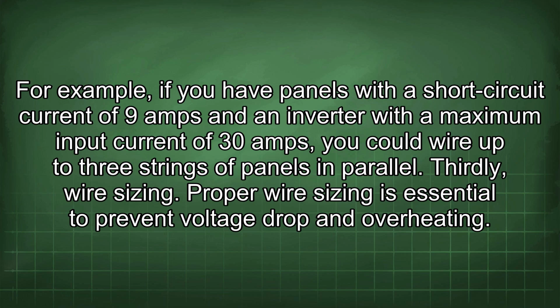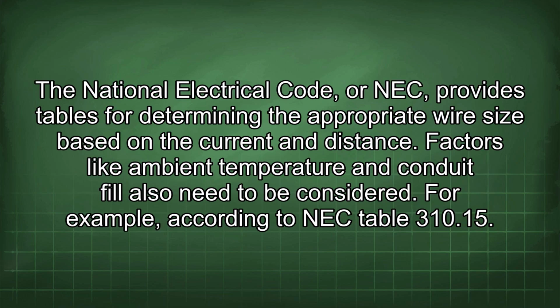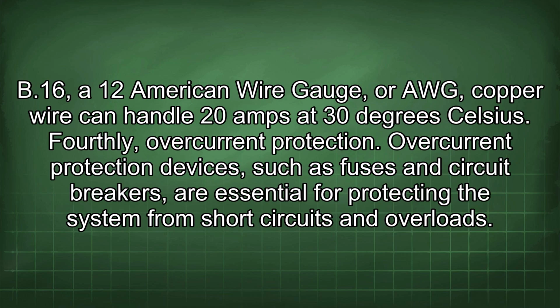Thirdly, wire sizing. Proper wire sizing is essential to prevent voltage drop and overheating. The National Electrical Code, or NEC, provides tables for determining the appropriate wire size based on the current and distance. Factors like ambient temperature and conduit fill also need to be considered. For example, according to NEC Table 310.15(B)(16), a 12 American Wire Gauge, or AWG, copper wire can handle 20 amps at 30 degrees Celsius.